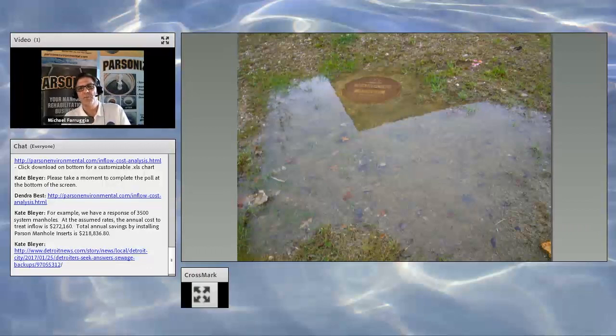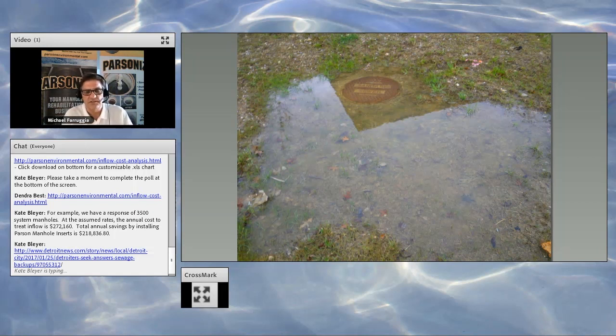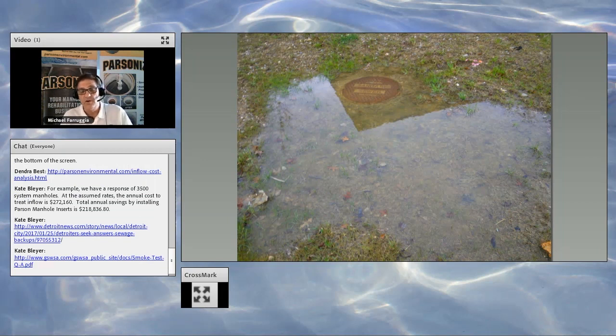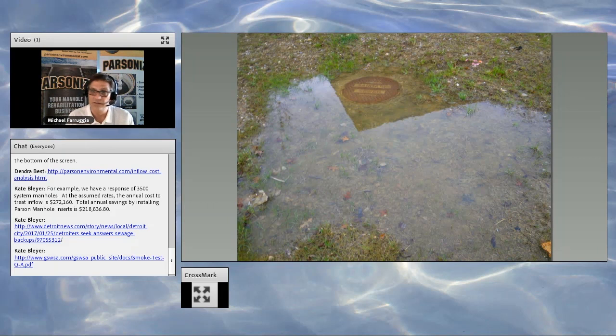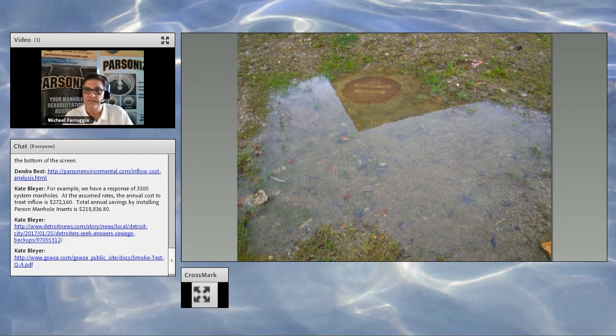We're going to talk about managing and controlling I&I. There are some expensive ways and some not-so-expensive ways. A couple of the more expensive ways are things like smoke tests — what they do is inundate the sanitary system with smoke and then look for points of leaking. A good example: if you inundate the system with smoke and you see three or four people's gutters on the street starting to smoke, you can be certain those rain gutters need to be disconnected from the sanitary system. Another way is engineering studies and flow studies, which can be very expensive — video cameras, inspections, things like that. These are necessary to identify problem areas, but they basically identify the issue — they don't stop it.